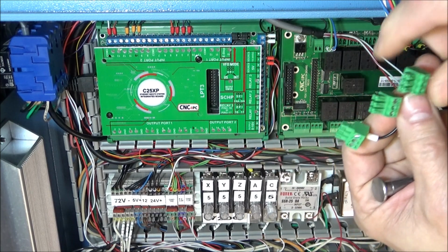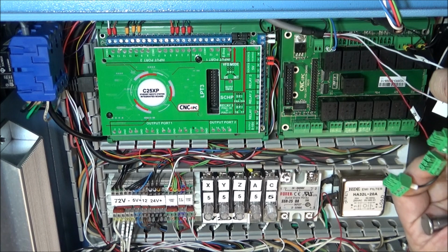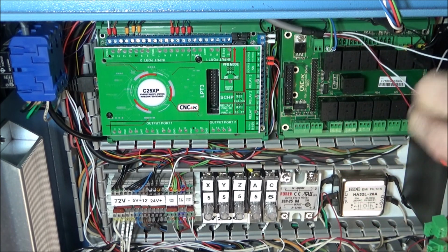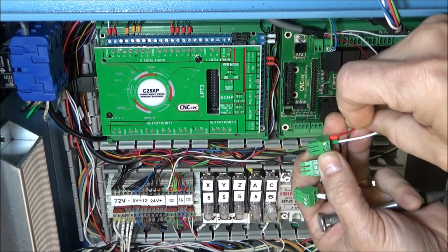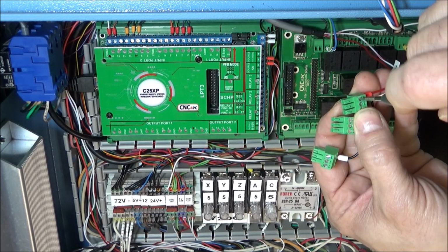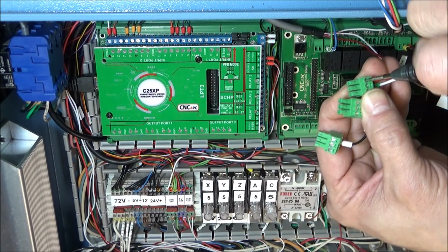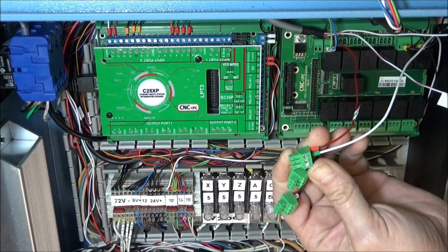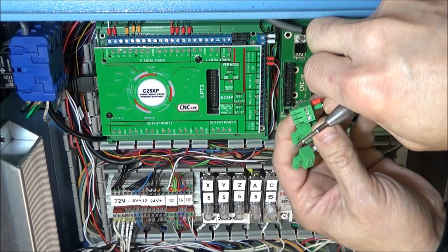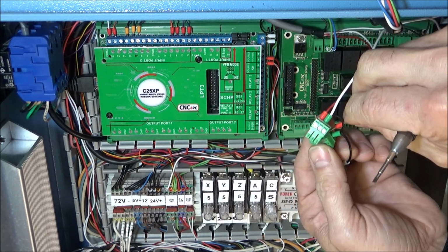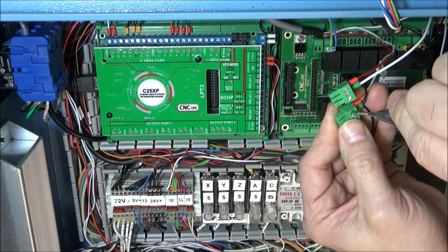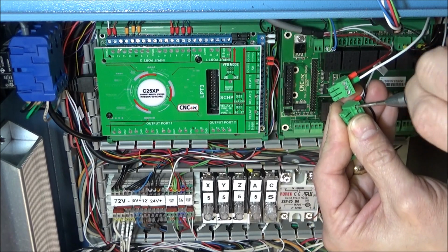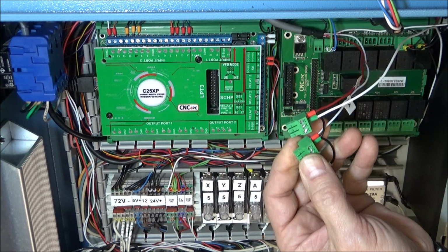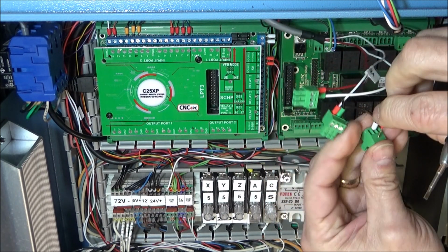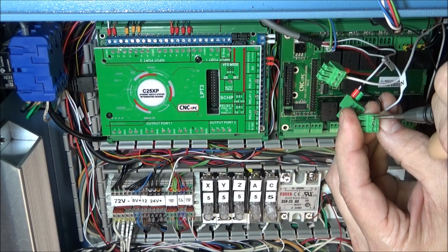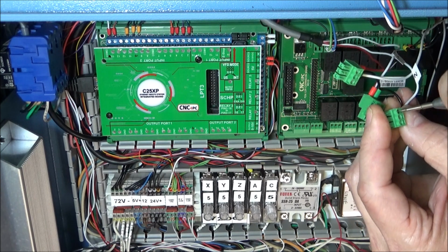And then next we just need to land our returns for each lamp. So the first stack light is going to be red, which is our red wire here. So that goes to our normally open. And then we have our amber or yellow. Our second relay. Again, it goes to the normally open side of the relay. And then last is our green over to the normally open for the third relay here, or fifth relay on the board.